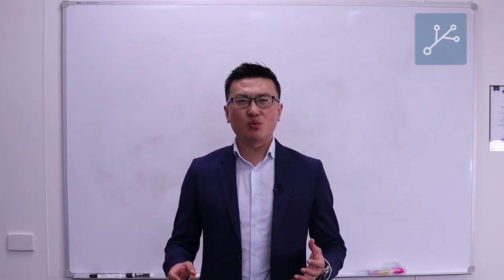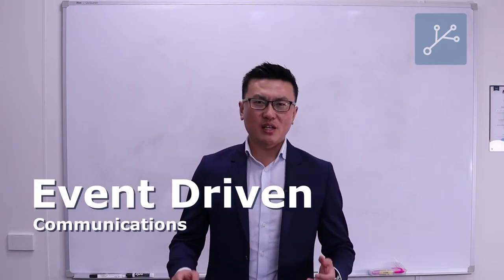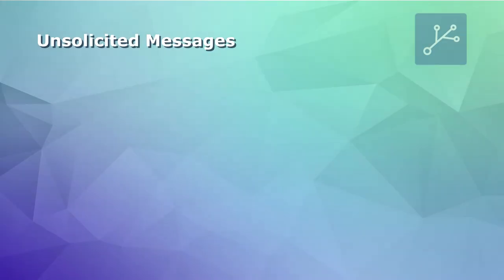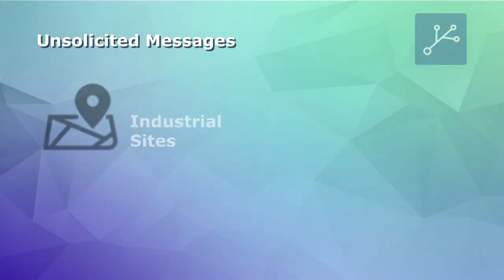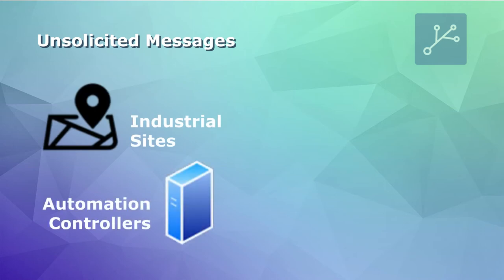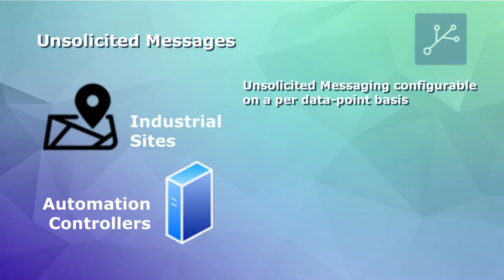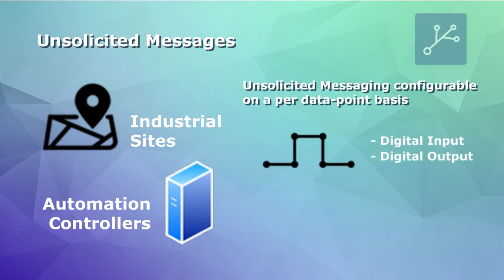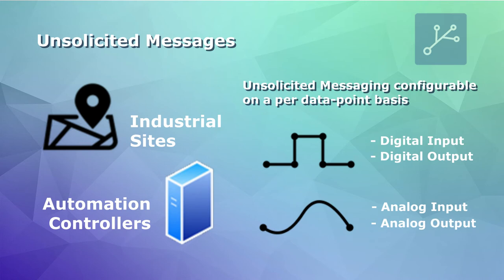People use DNP3 with event-driven communication by configuring unsolicited messages for each site or for each controller. The unsolicited messages can be configured per data points — that is digital input, digital output, analog input, and analog output. It can also be configured for counter objects as well.